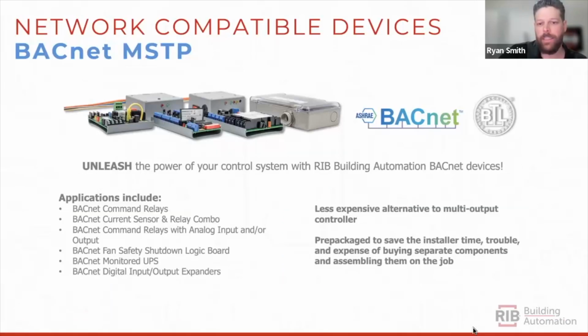This product fits into our network compatible devices category, where we already have many products that communicate over BACnet MSTP. These products feature command relays, relay and sensor combos, relays with analog inputs or outputs, fan safety shutdown boards, monitored UPS solutions, and digital input-output expanders. The BACnet products in this category are made to save the installer time, trouble, and expense of buying separate components and assembling them on the job site, and are a less expensive alternative to adding I/O modules to a panel. Now Henry can walk us through how to set up the BACnet IP relay.